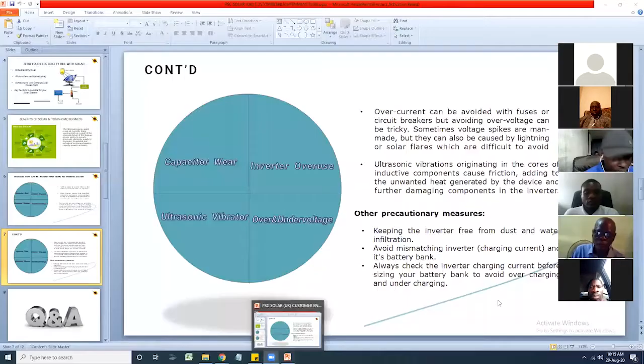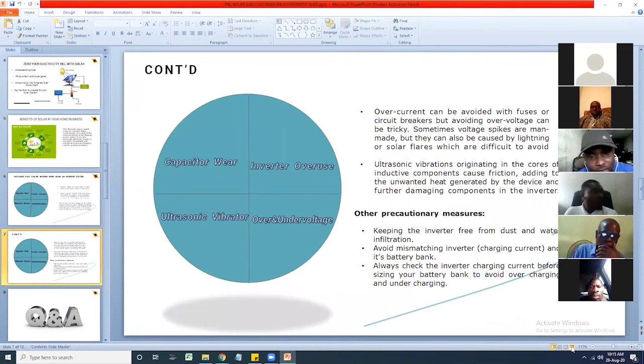The next one here is avoiding mismatching the inverter and your battery bank. Now, this is another very important area. Whenever you want to purchase an inverter system, you always make sure you check the rated charging current of the inverter system before you size any battery bank. Let's say, for instance, you have a 1.5 kVA, 1.4 kVA inverter, which we know typically has about 20 amps maximum charging current. You cannot use 6 batteries for that kind of inverter. You have to remain within the manufacturer specification of 2 units of 200 amp battery.